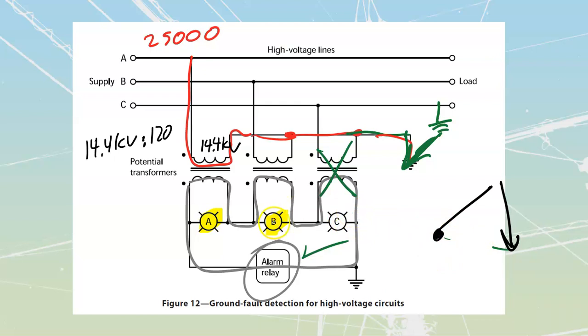The other two lights are actually going to increase, because if this one has dropped away to 0, closing this one off, these two are going to go from 14.4 kV all the way up to 25,000 volts, 25 kV. So we need to make sure they're rated to handle that. When they jump up, the value of voltage on our secondary is also going to jump up.